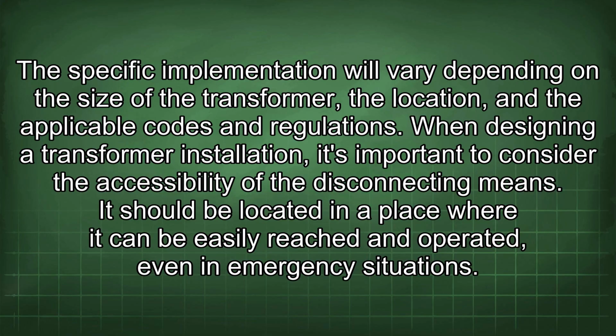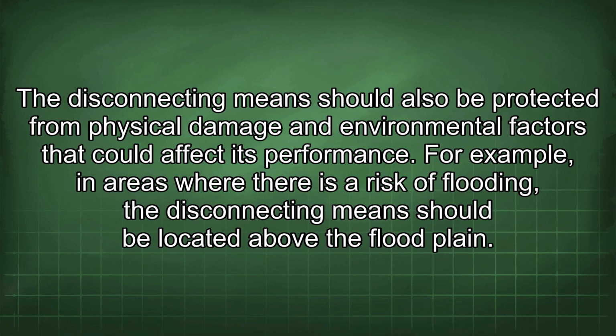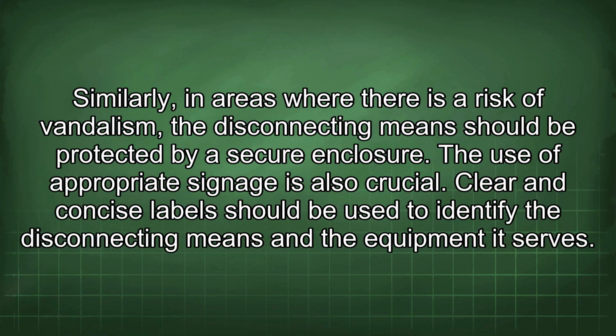When designing a transformer installation, it's important to consider the accessibility of the disconnecting means. It should be located in a place where it can be easily reached and operated even in emergency situations. The disconnecting means should also be protected from physical damage and environmental factors that could affect its performance. For example, in areas where there is a risk of flooding, the disconnecting means should be located above the floodplain. Similarly, in areas where there is a risk of vandalism, the disconnecting means should be protected by a secure enclosure.